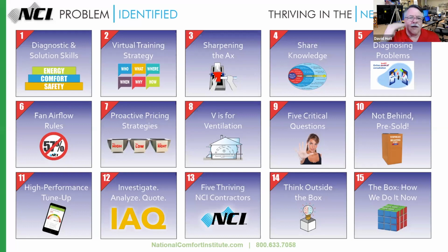So when Goodman Amana builds a 98% furnace, guess what? We're only getting 57% of that capacity to the home. When Goodman Amana builds an 18 SEER, 20 SEER system and we start throwing this good inverter technology in, guess what? Only 57% is getting to the home. Why is that? Well, it's not because of the equipment -- it's because of poor installation practices.